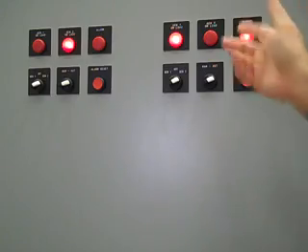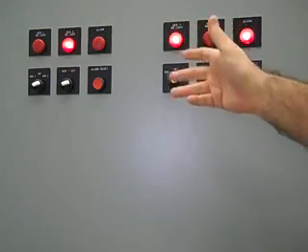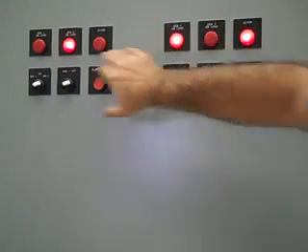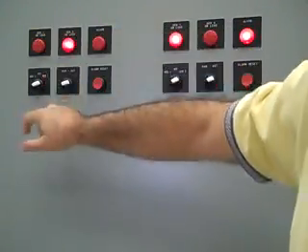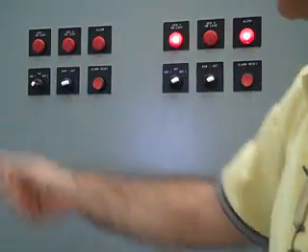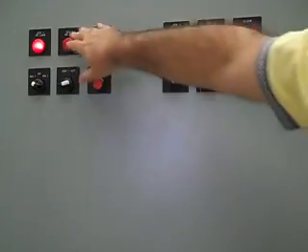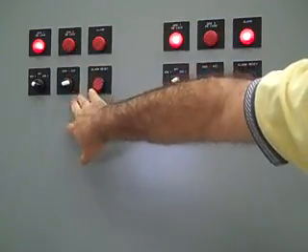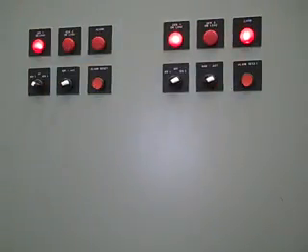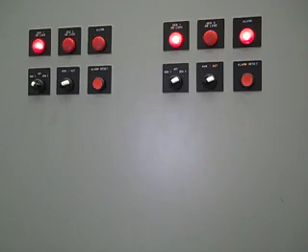Now, let's say you had the situation, and right now because you have 3 generators, you say, okay, I don't want to run a big generator and a small one. I want to make this other switch also go to generator 1. You can do that by flipping the switch, and you go to generator 1, and eventually generator 2, after your cool down time, will turn off, and you're going to keep running both switches or both sides of the island with the same generator.